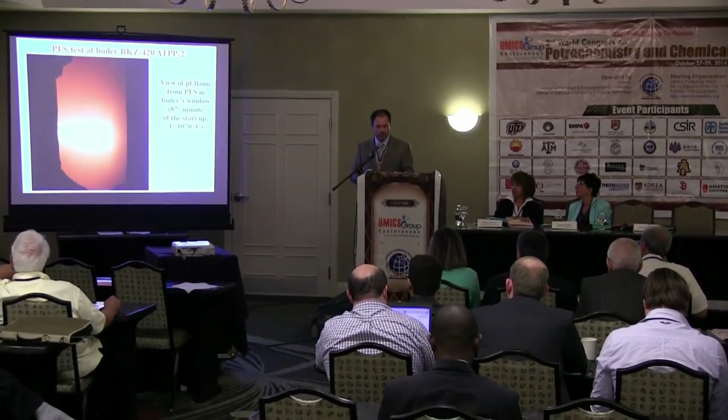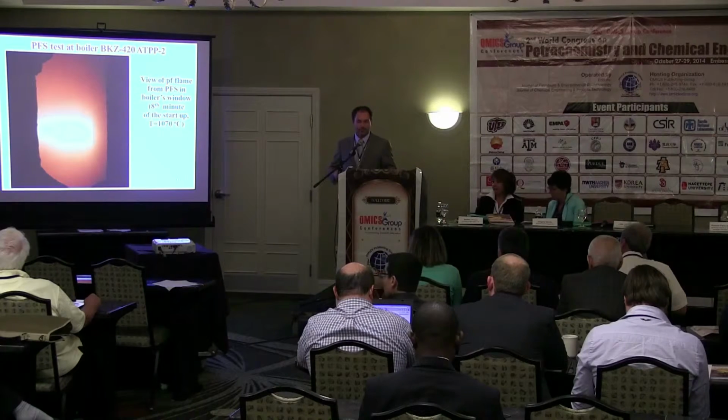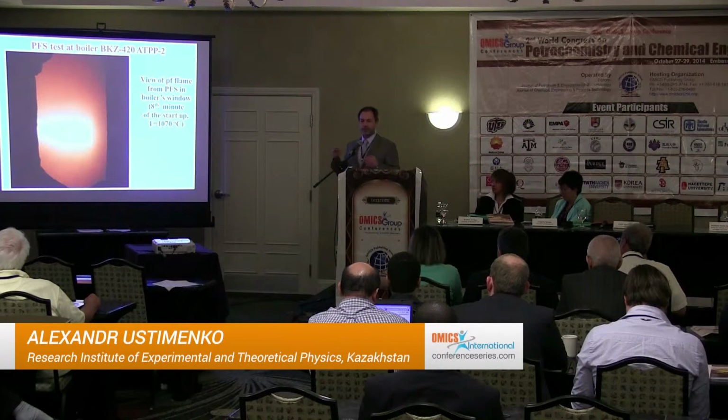And the temperature of this flame was measured, and you can see that the temperature was a little more than 1000 degrees centigrade. So using this flame, we can warm up the volume of this boiler furnace, and the process of startup can be done without use of fuel oil. So we use coal instead of fuel oil.